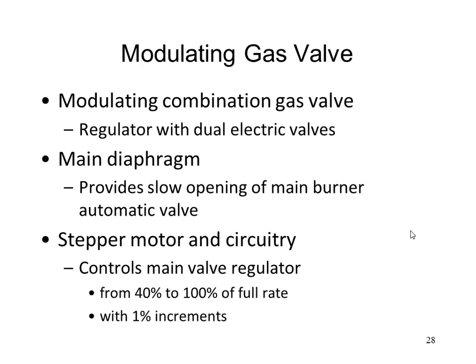Like we said, that guy is a 40 to 100% modulating valve in 1% increments. So it goes from 0, and then it skips 1 through 39 obviously and starts at 40. 40 is the minimum firing capacity. But then it can go 40, 41, 42, 50, 60, 80, 88, 90, 100, all the way up. So 61 individual steps.